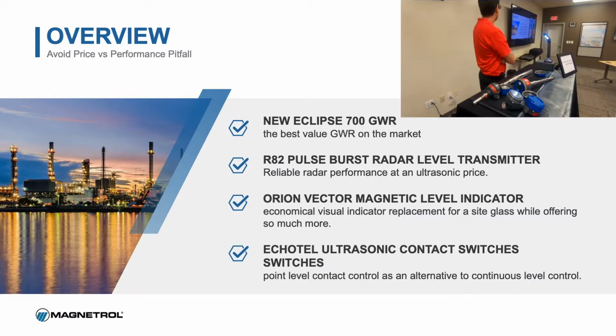So the overview of what we're going to cover: we initially had titled it The Right Chemistry for Level Control, and then Avoid the Price versus Performance Pitfall. But what we're going to go over today is 4 products. The new Eclipse 700 guided wave radar that we just released, an R82 through-air pulse burst radar level transmitter that's low cost with high performance, a lower cost magnetic level indicator that we call our Orion Vector, and then we're also going to show EchoTel ultrasonic contact switches, for a unique application idea where we could use these directly as level controllers, a low-cost solution. The first 3 products are lower cost continuous level measurements, and the EchoTel switches use contact switches for level control. So it's just an alternative to regulatory continuous control. So these are the topics.